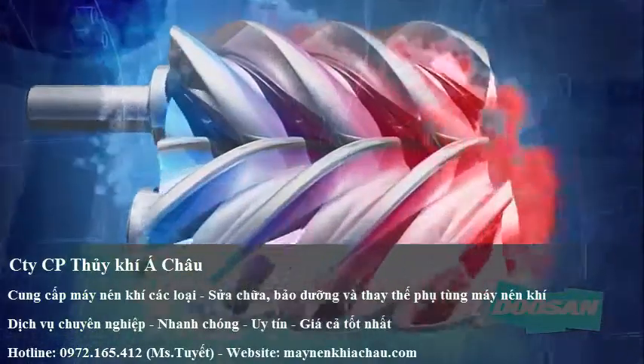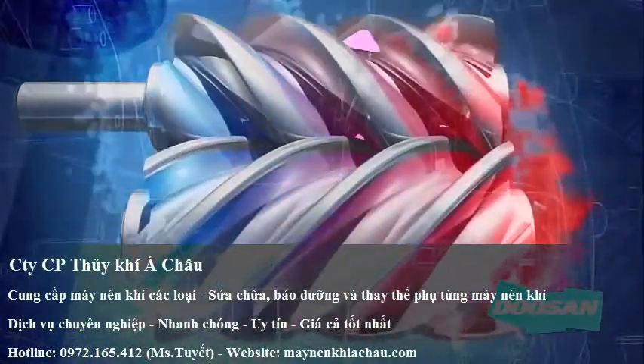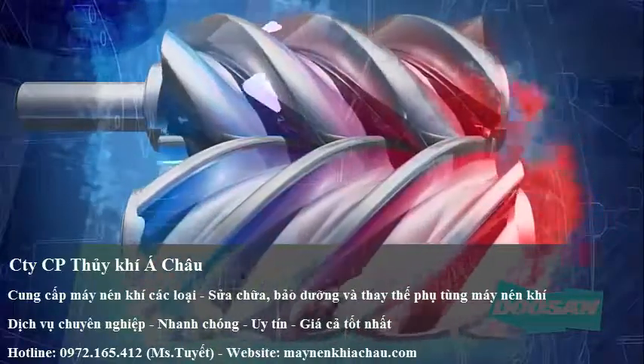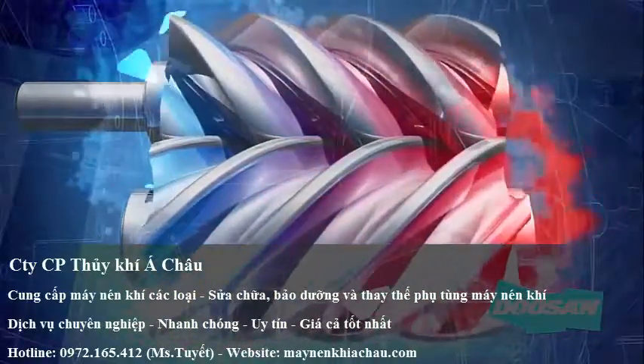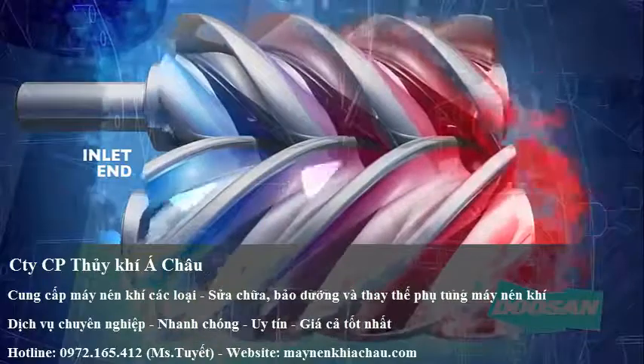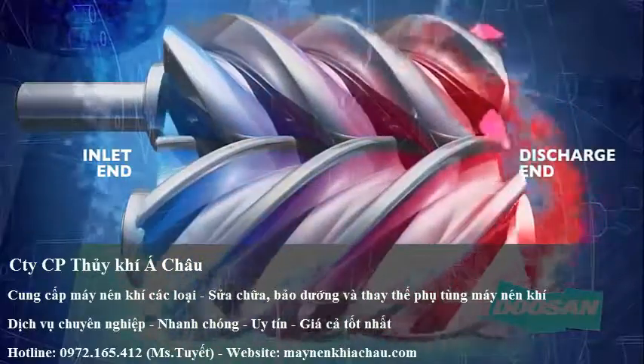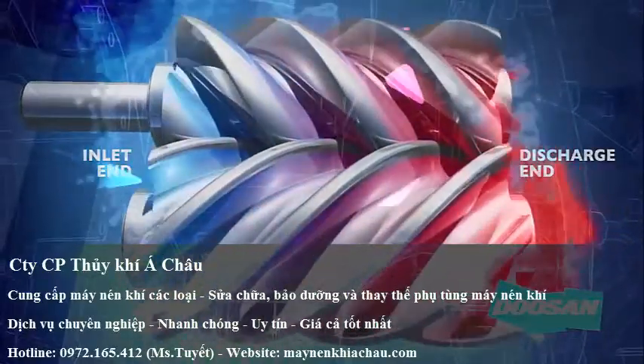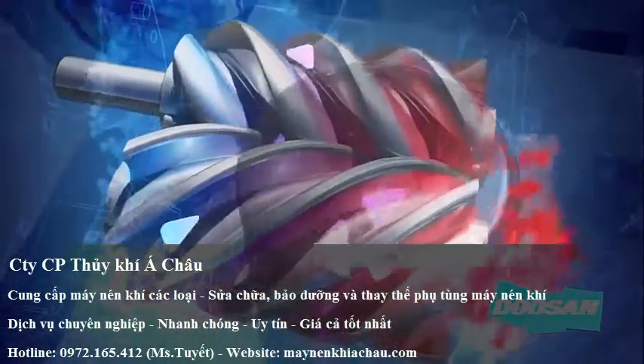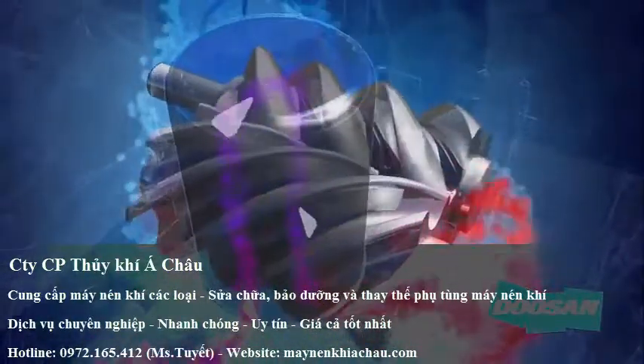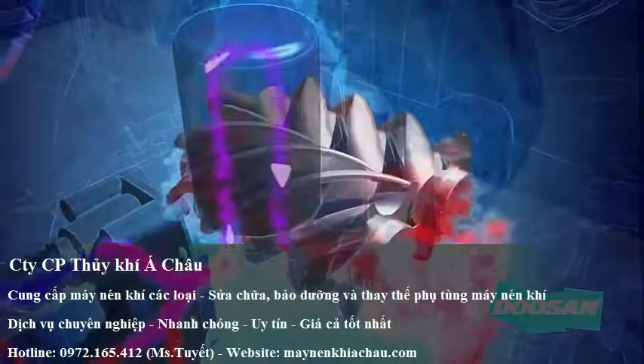As air travels along the helical rotor flutes, the space occupied by the air gets progressively smaller. Since the air cavity between the rotors is larger at the inlet end and smaller at the discharge end, air becomes compressed, creating significant heat. During the process, oil is injected into the rotors and serves three critical purposes.